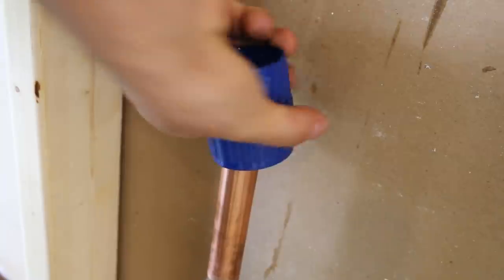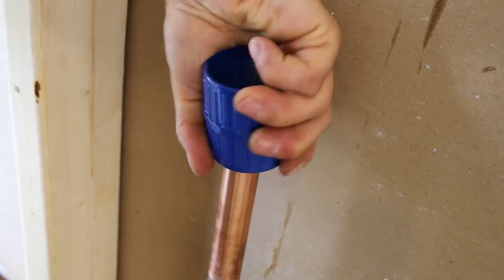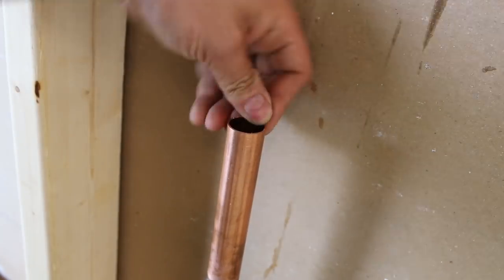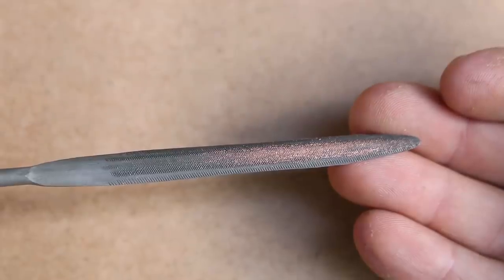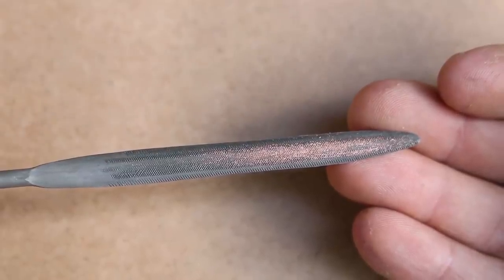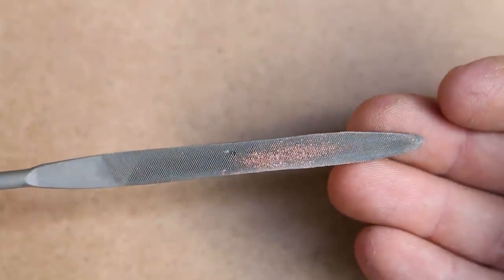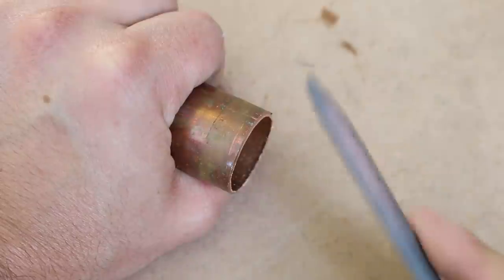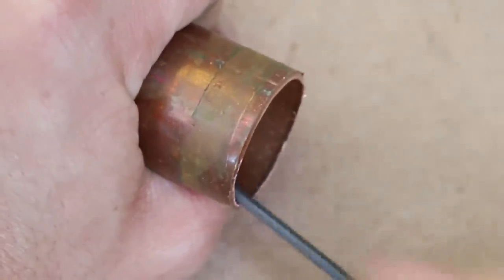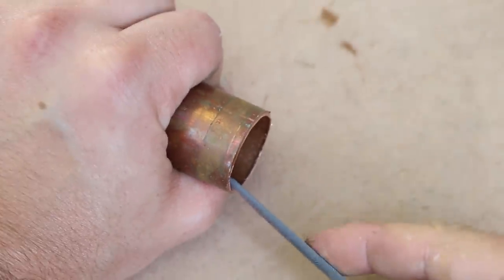So how do I deburr a pipe? For those who haven't done it before, deburring is quite simple and easy to do. If you're using a file, make sure you get one that is half round on one side and flat on the other. The flat side will be used for the outer burr and the half round side for the inner burr, just like this.